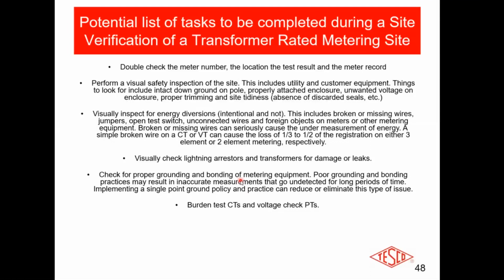Had a utility tell me the story last year at a meter school. They got a call from a customer. They'd moved out of a manufacturing site. It was an old Quonset hut, and the customer called and said, hey, we just got a bill for $30,000. The place has been empty for 3 months. We usually get a bill for $50, $60. Something's wrong. They went out to the site. As they opened the door, the Quonset hut was live.